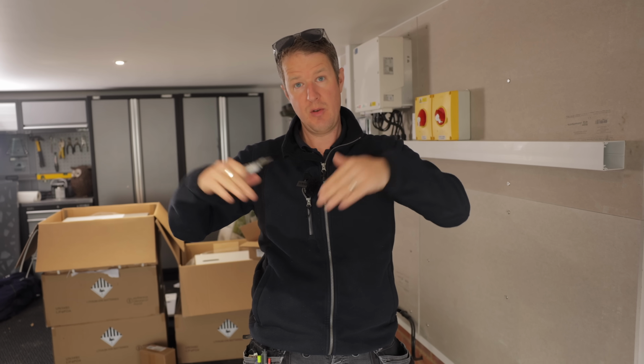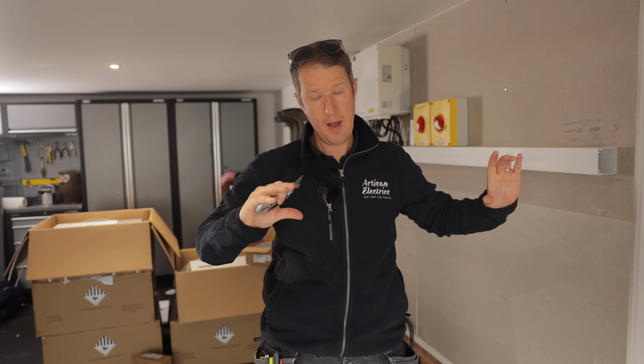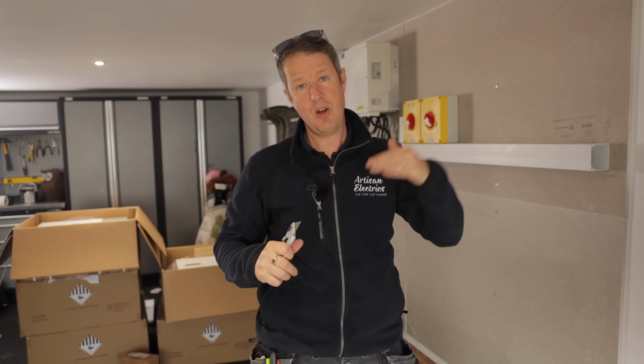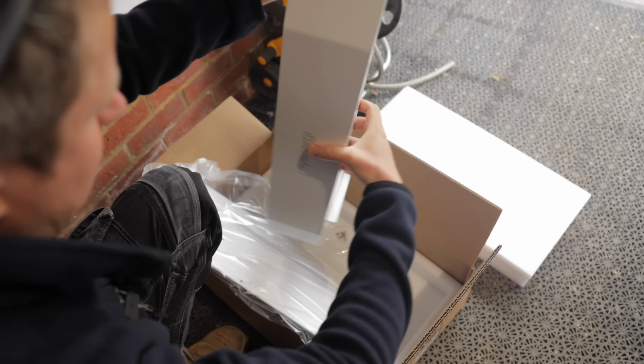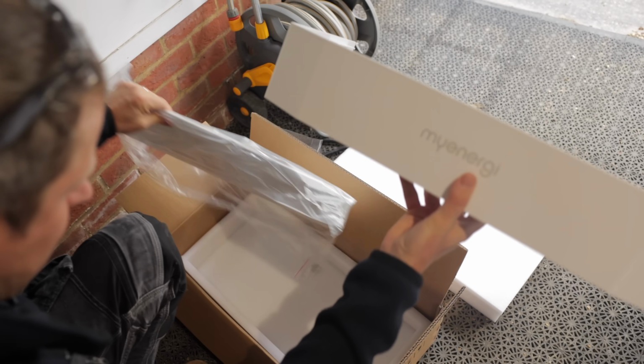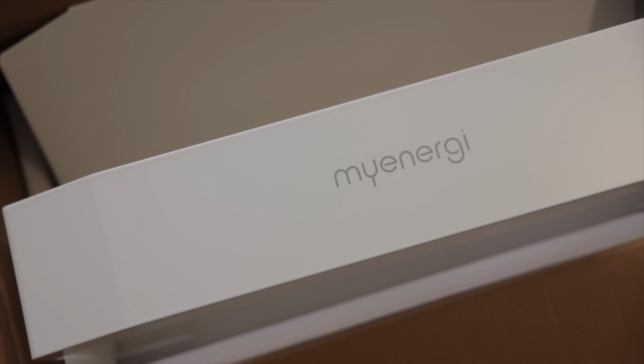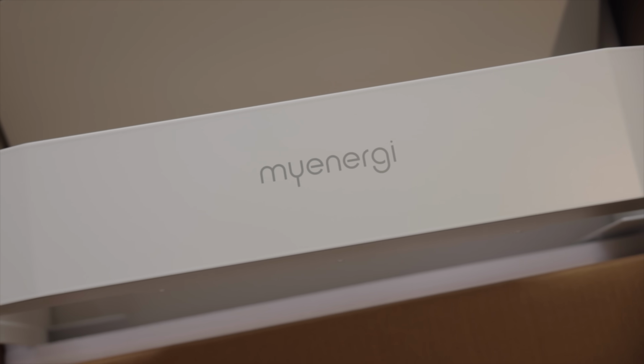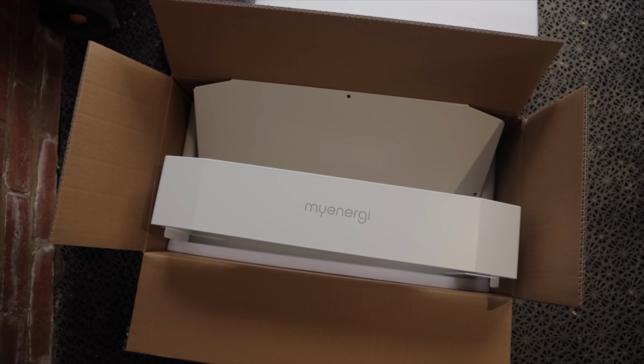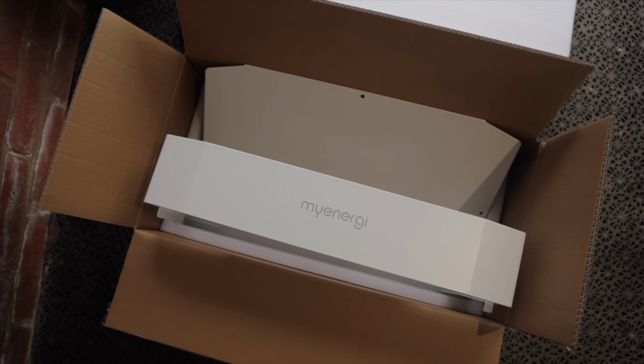Now, one thing I've seen, and we nearly forgot once, is the top cover for when you're doing 2 stacks of batteries. Obviously with the normal 10 kilowatt hour kit, you've got the Libbi inverter at the top, so you don't need a top cover for that battery. But if you've got a second stack of batteries, you need an additional top cover to neatly finish off the top of that stack. That's what this is. I've seen some people install them without it, and it's doable, but it just looks really ugly. So definitely add a top cover to your order if you're ordering more than 10 kilowatt hours worth of batteries.